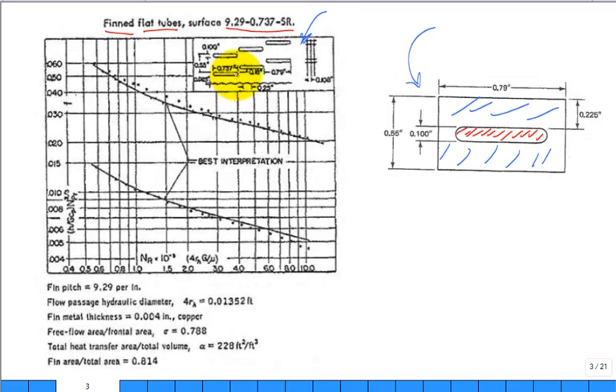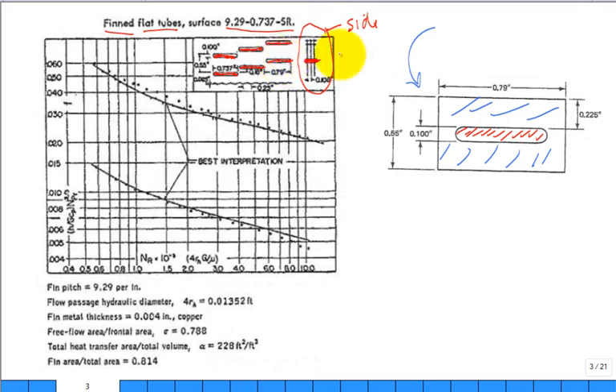You can see the flat tube passages and the plate fins connecting them. There's also a zoomed-in side view showing the passage for the water and the fins. The fins aren't just straight — they have kinks in them, which promotes heat transfer on the air side by causing the flow to oscillate slightly.